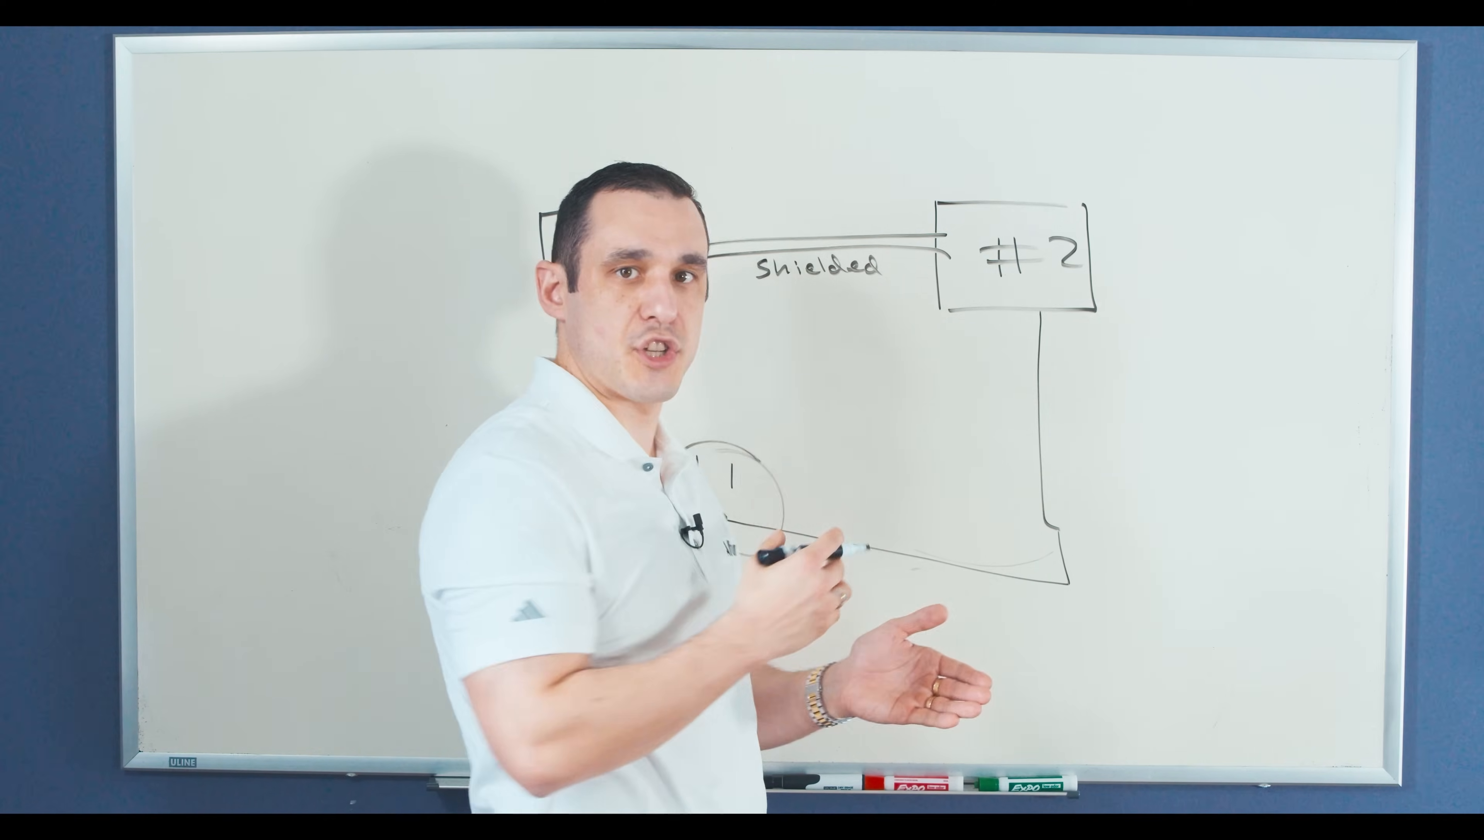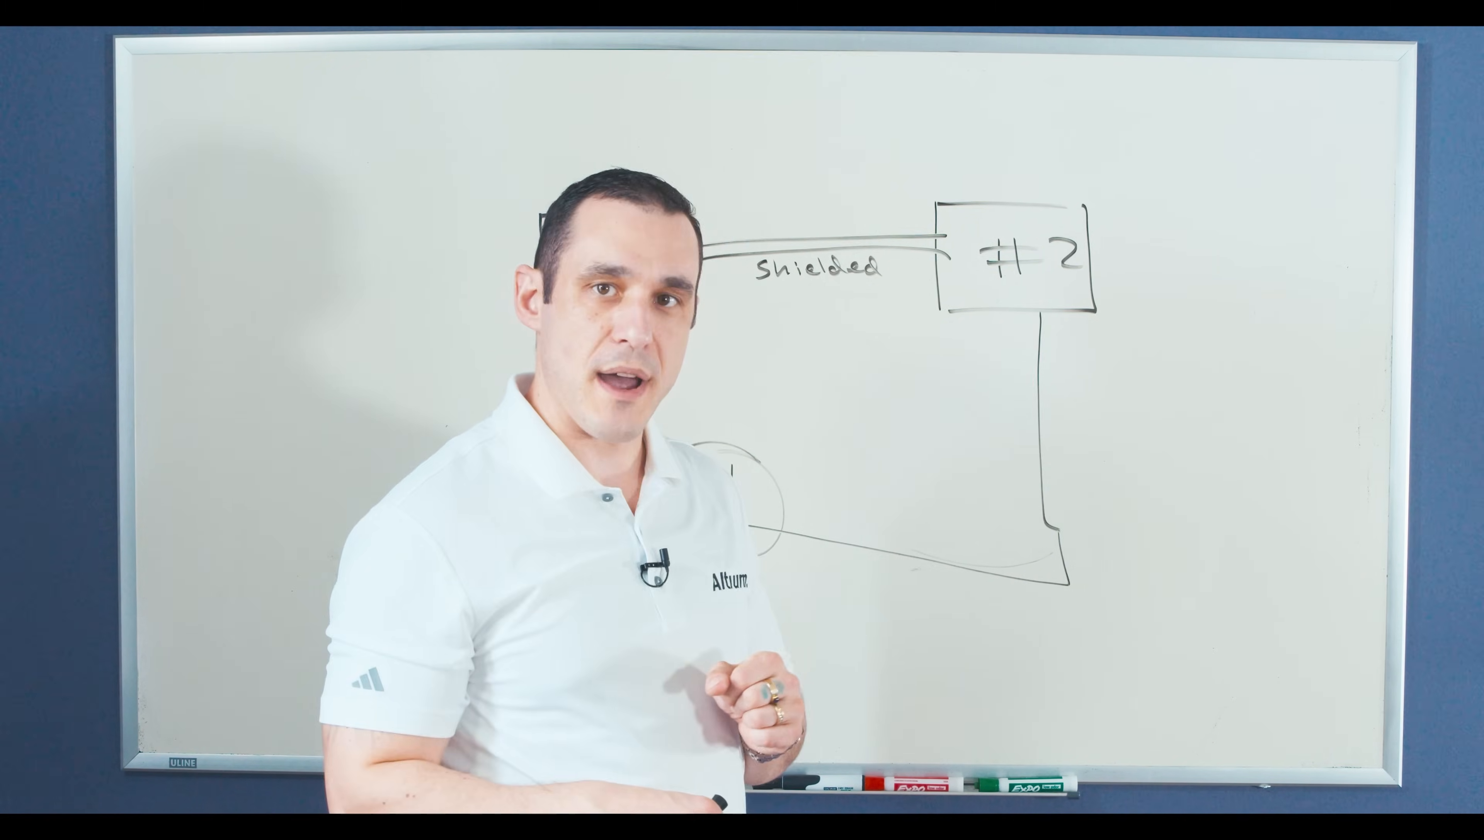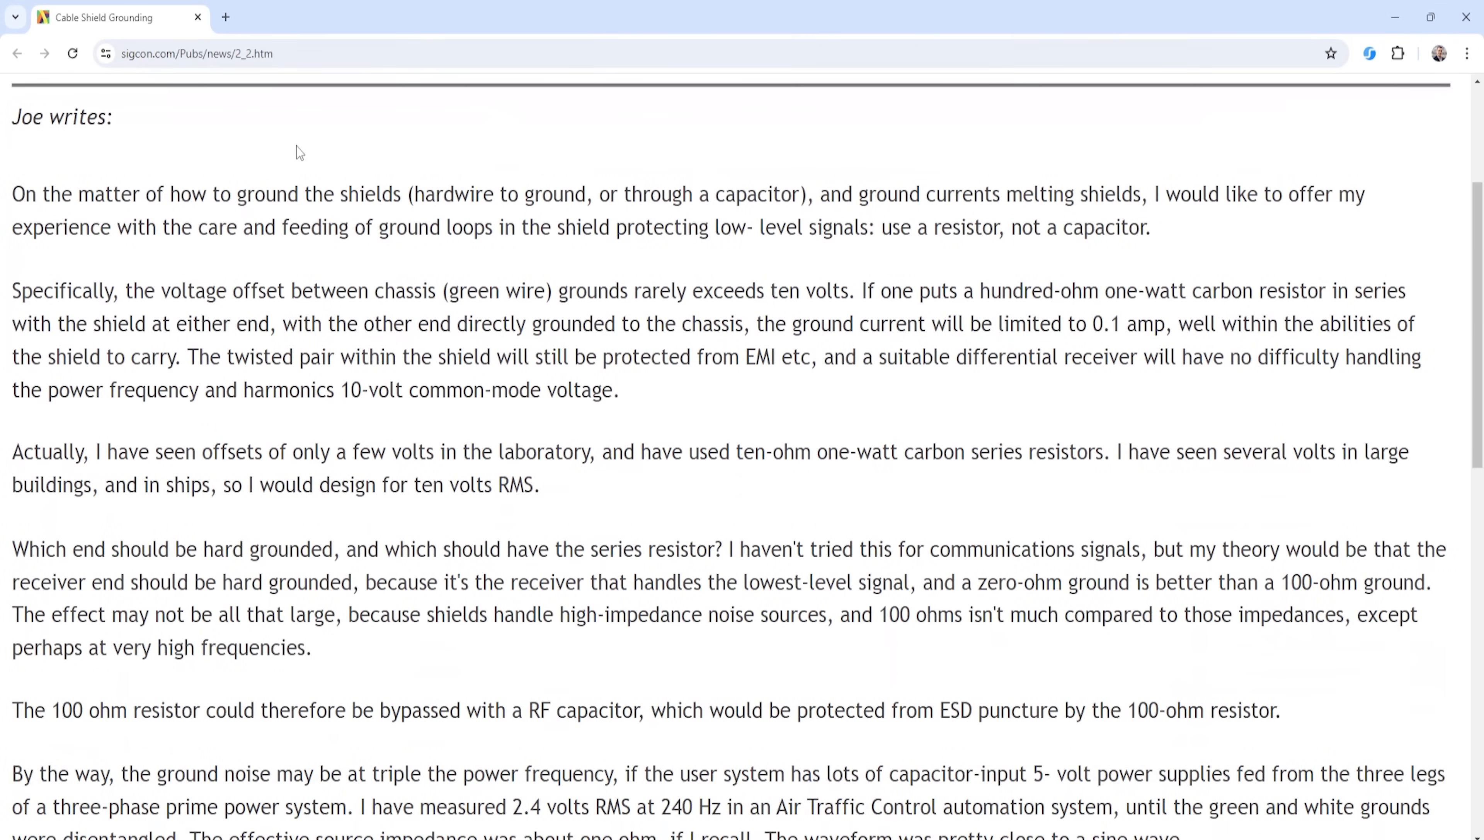Now if we did have a ground loop going on in this system, what kind of potential offsets could we expect to then drive a current over this shielded cable? Well, let's take a look at some advice on Howard Johnson's website to see what those voltages might be. So here on Howard Johnson's website sigcon.com, there is an article on cable shield grounding, and you can see here that there's a guy Joe who recounts his experience looking at the voltage offsets between the chassis grounds, and you can see here in his correspondence, the voltage offset between chassis grounds rarely exceeds 10 volts.